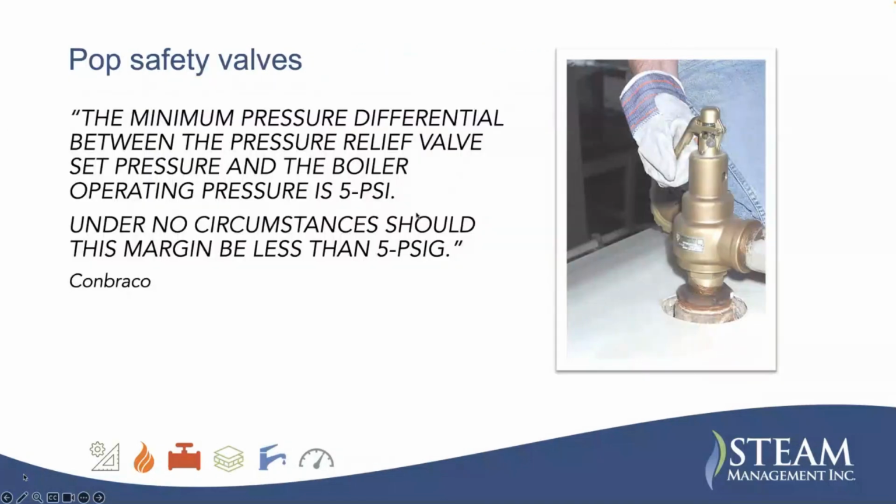Here's what I talked about, where Conbraco says, under no circumstances should this margin be less than 5 psi. So if this is a 15 psi relief valve, they don't want you running your boiler higher than 10 psi.